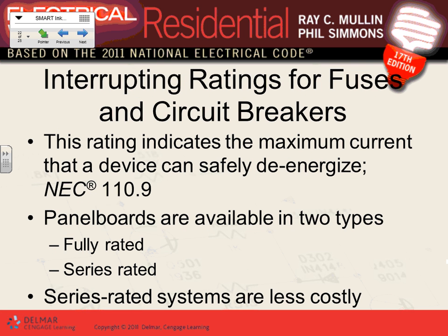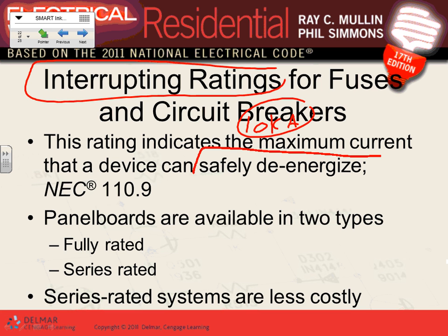We talked about, guys, the interrupting rating of circuit breaker. When we say 10,000 amp, this is how much a circuit breaker can safely interrupt short circuit or ground fault. Higher than this, big ball of fire. Cool? Okay, any questions? I can't emphasize the word safely enough, safely de-energize, because we can de-energize a lot of things unsafely. Right? We're going to safely de-energize. Any comments, any questions about circuit breakers?